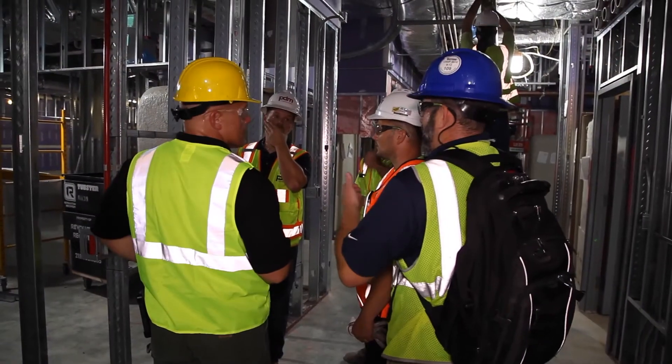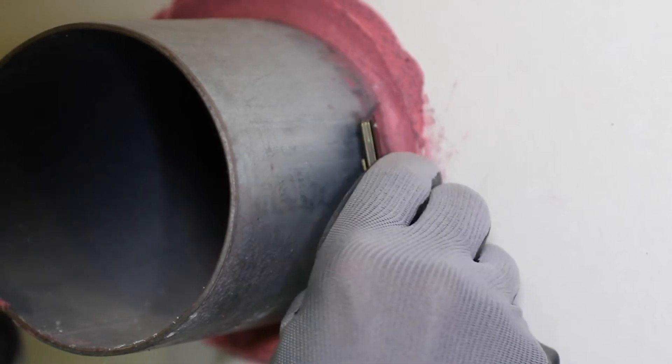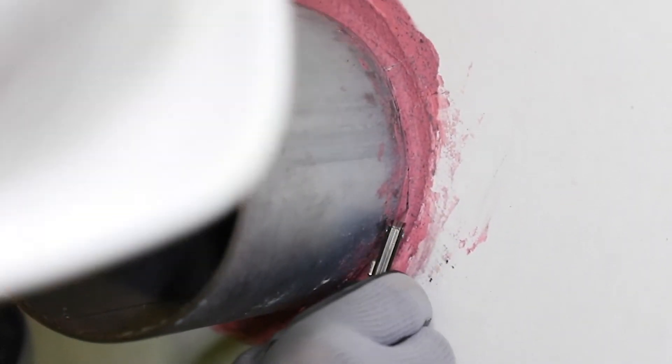In order to inspect fire stop systems, they must not be concealed from view before being inspected and approved. Walkthrough visual inspections should be made during installation as required. However, destructive testing may be necessary to evaluate certain types of fire stop systems after they have been installed.